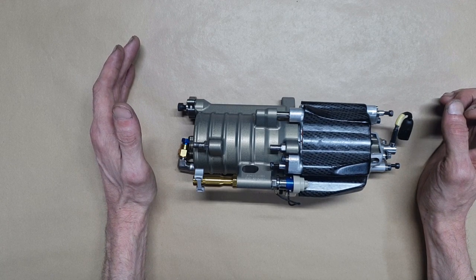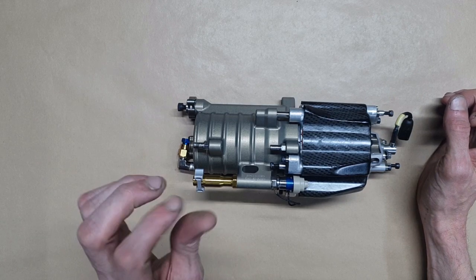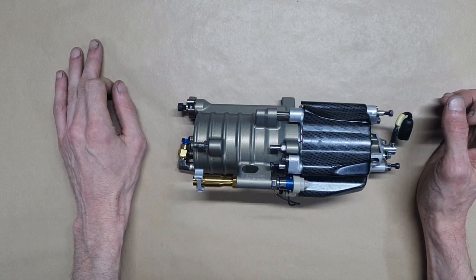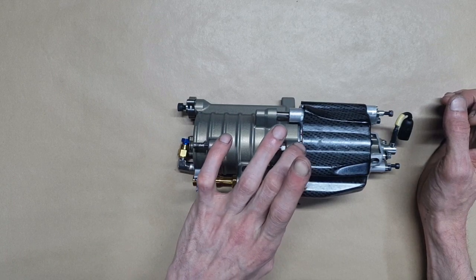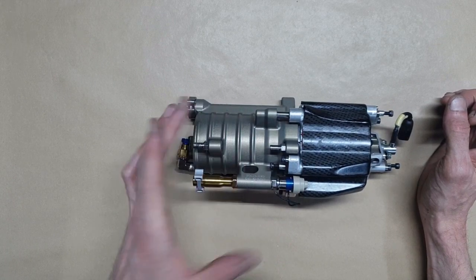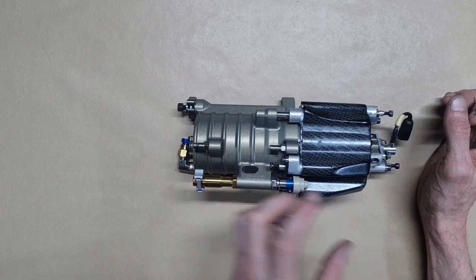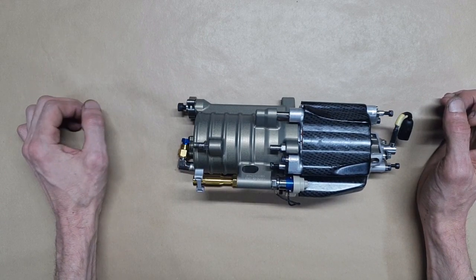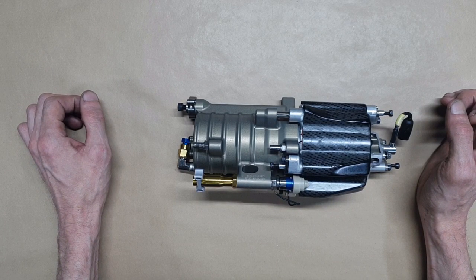Whereas if a diaphragm type accumulator fails, it'll just be gone in a second. Whereas this will fail slowly, because it's like a single action ram with nitrogen behind it and oil in front of it, so it tends to fail a lot slower.